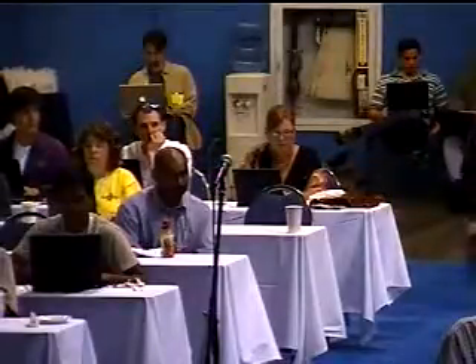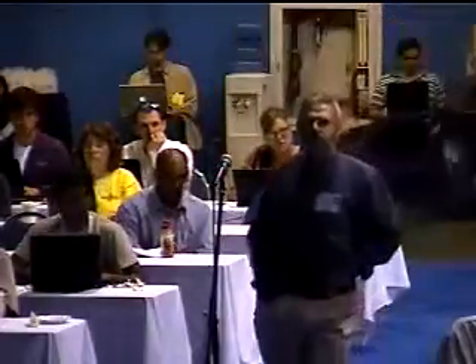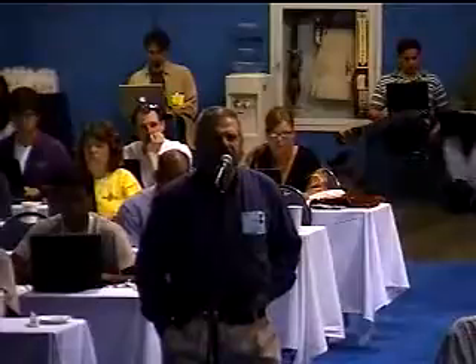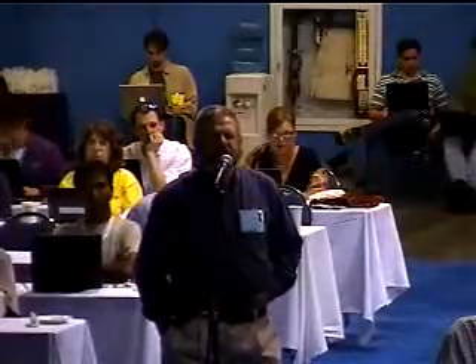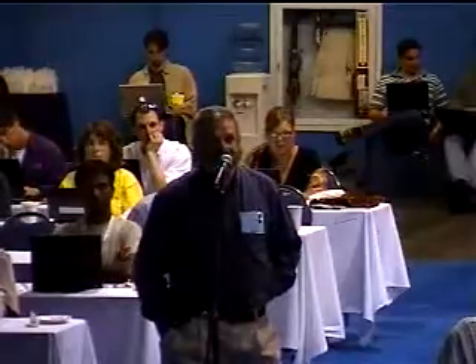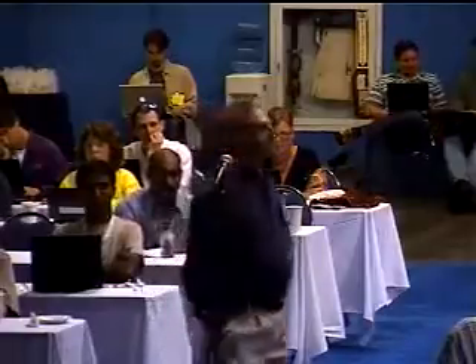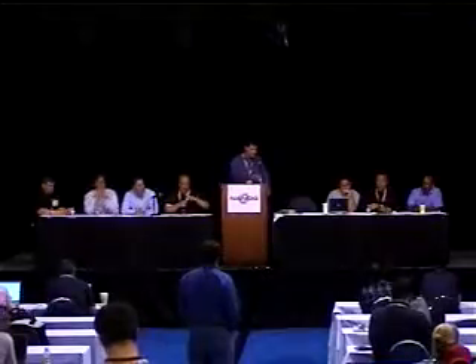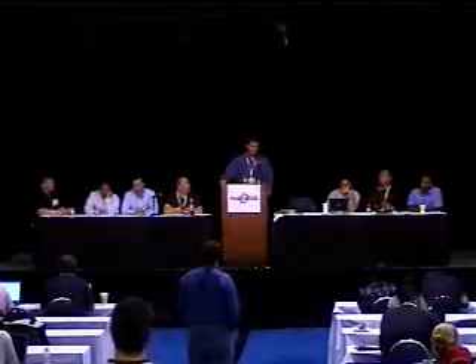Currently, we are... Equinix is building like 4 kW per cabinet in the future. We're already planning on it, building going forward into 2007. It takes about close to a year and a half to start. A cabinet is about 2 square meters, essentially, because you have to walk down the aisle. So that's 2 kW. So anyways, going forward, we're building that data center. And going forward, we actually are starting to separate high-density users, medium-density users, and low-density users. So that's what we're going forward with. I think that's the wave of the future, building high power density pods.